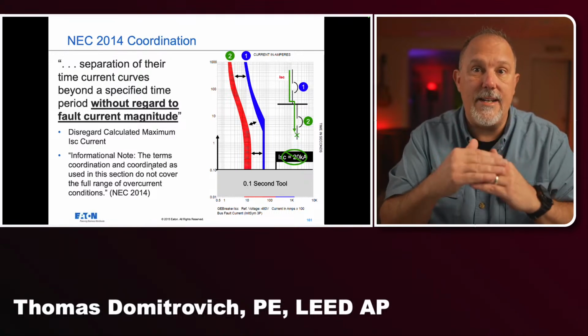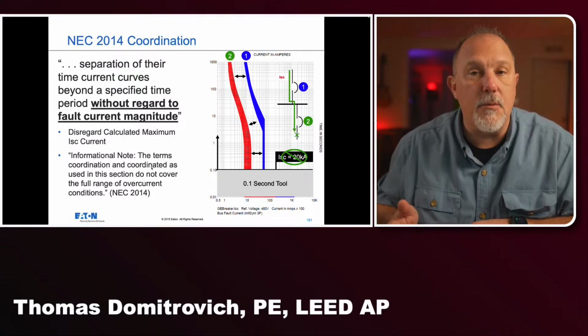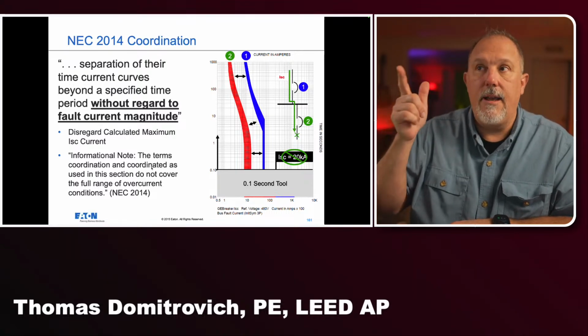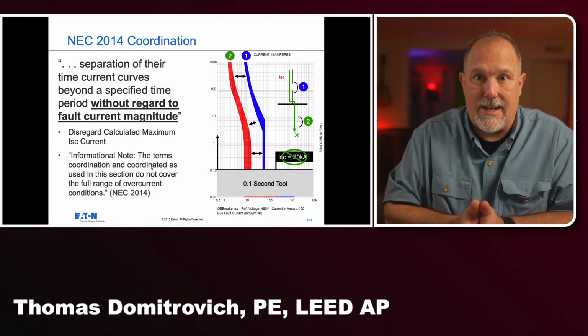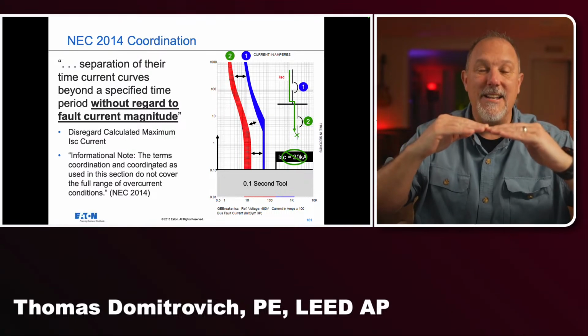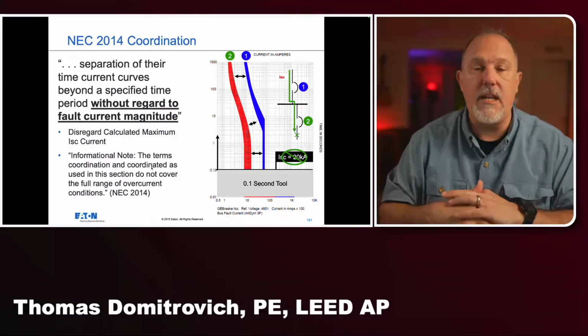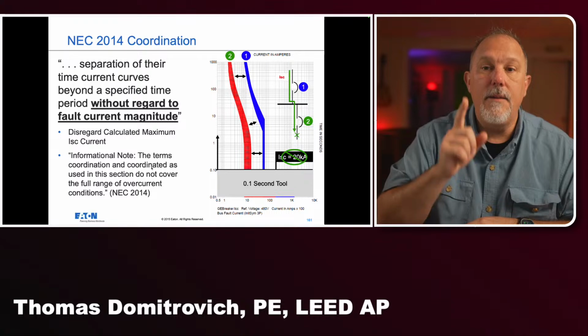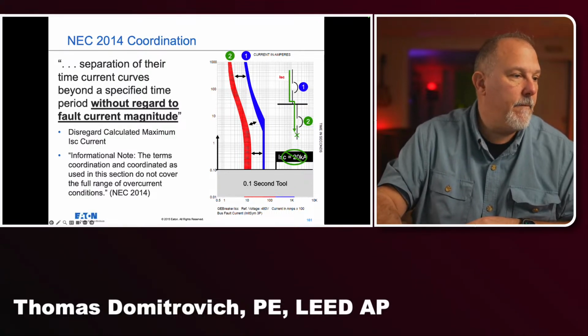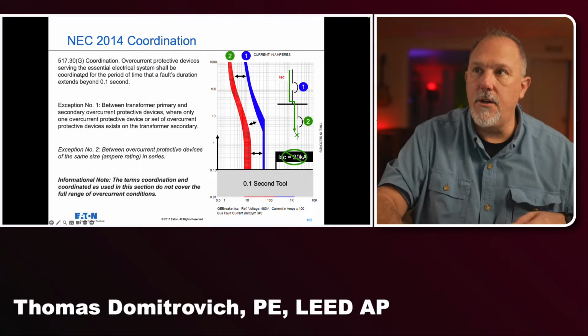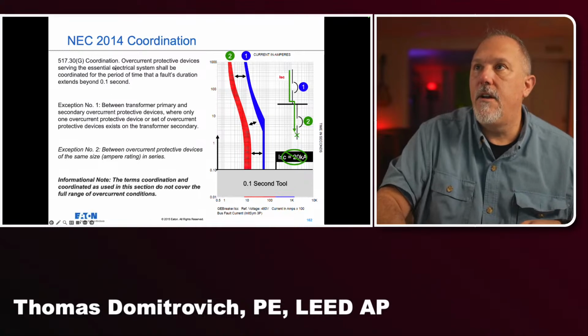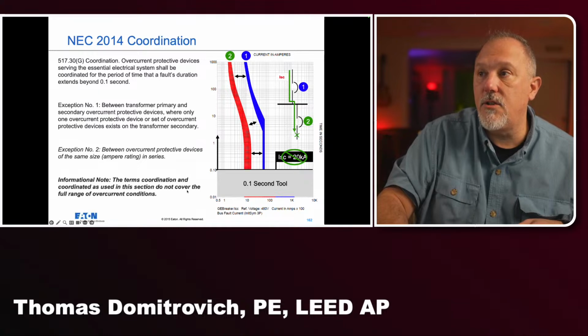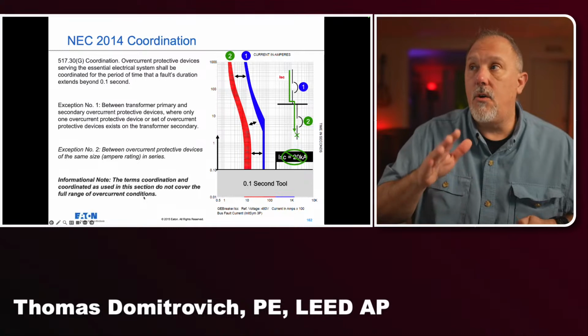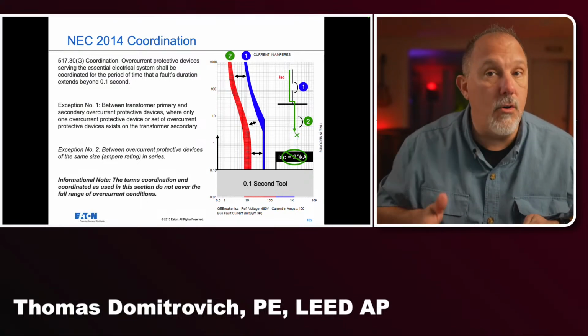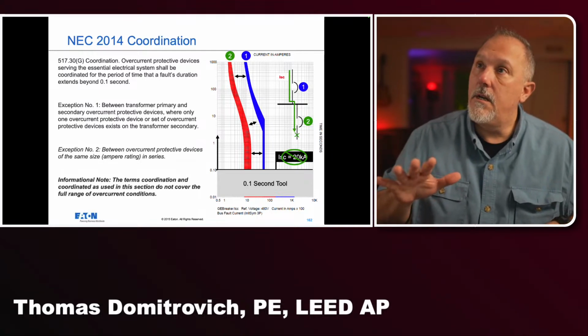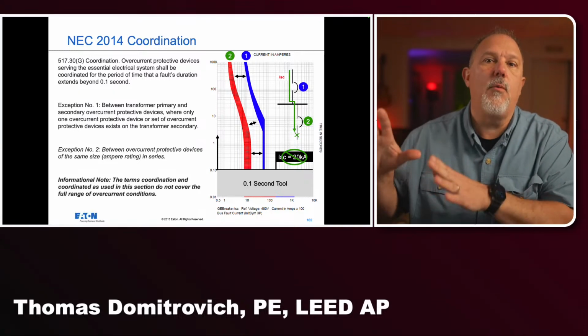So what we did, remember how you said, boy, it would be so much clearer if we expanded down to 0.001 seconds. What they did in healthcare was they ignored everything below 0.1 seconds. So they raised the bar, so to speak, in the time current characteristic curve to hide all of the problems underneath, but they still have to deal with fault currents, so they basically say they disregard that current. And if you look at the language in the code, informational note, the terms coordination and coordinated do not cover the full range of overcurrent conditions. So all they're doing in healthcare is looking at overload. That's it. I think that's clear. Hopefully that helps you understand what 0.1 seconds is.